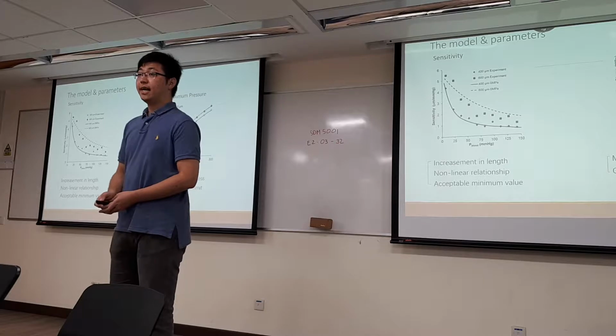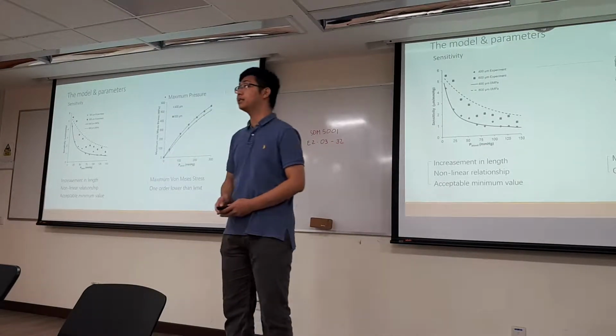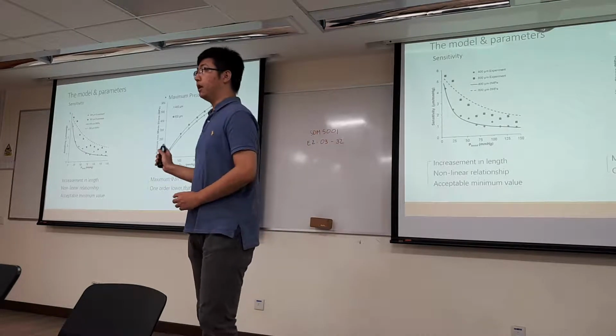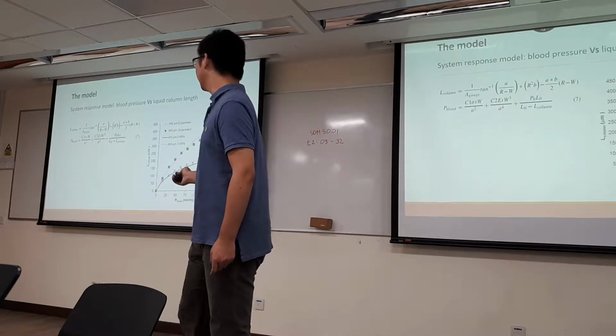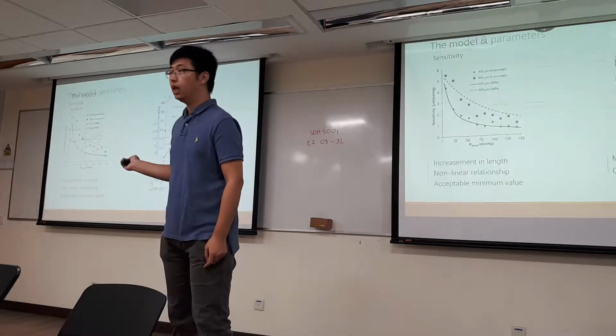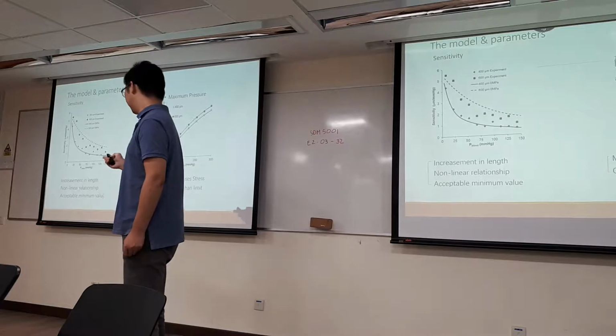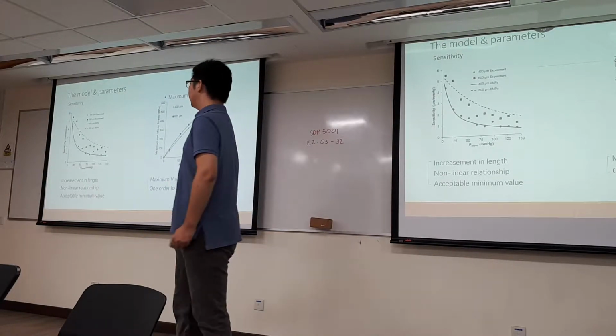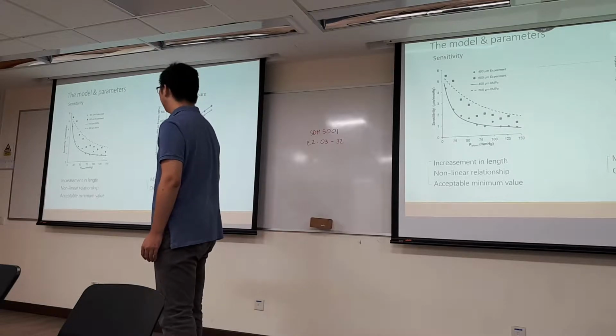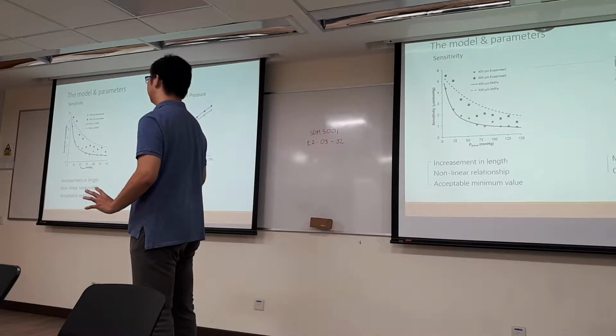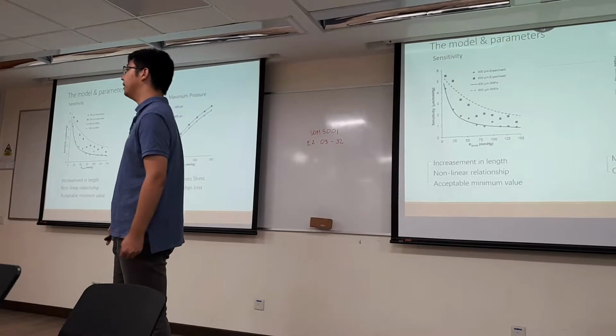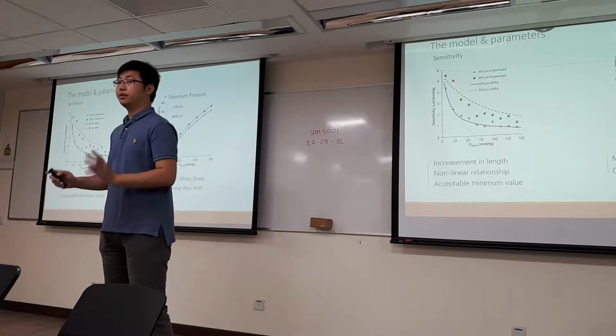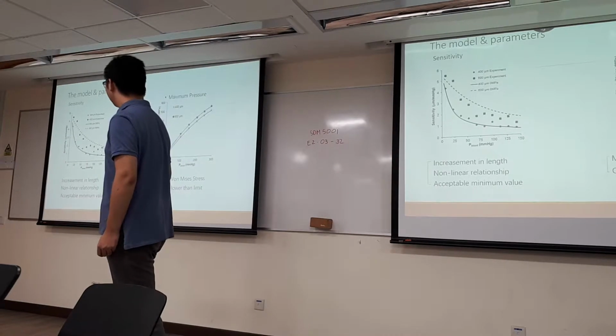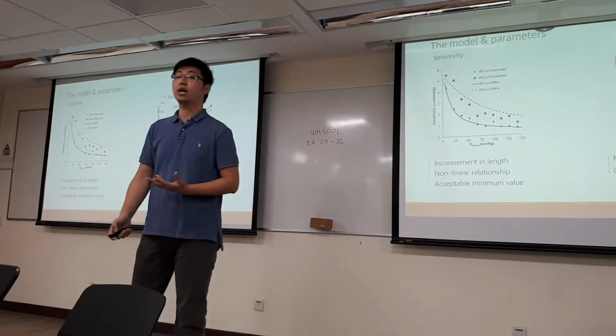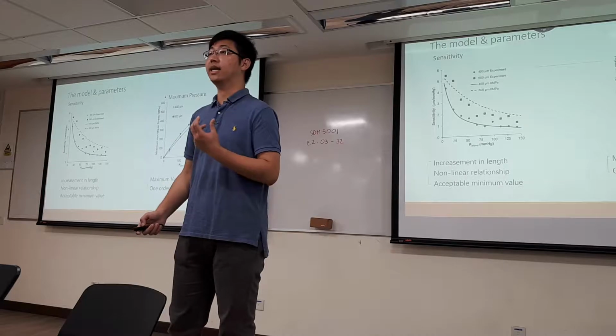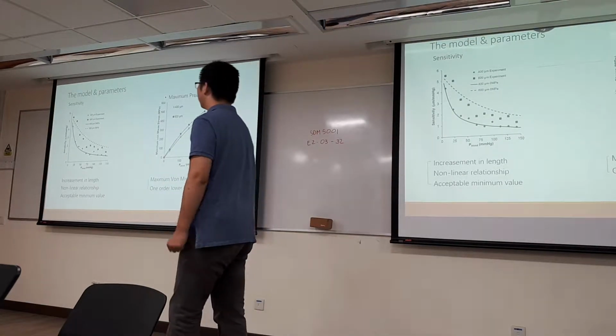Many other performances are also tested here. First thing is the sensitivity, which means the increase of the length at different pressures. In the previous slide, we can see that the relationship between the pressure and the length is not linear. So the higher the pressure, the lower the sensitivity. You can see here from this one. But even for the lowest sensitivity, based on current X-ray imaging technology, we are still able to see the difference in blood pressure when the restenosis happens. Of course, by using the lowest sensitivity, we cannot get a very accurate reading of the pressure, but definitely we are able to capture the pressure drop of the restenosis.